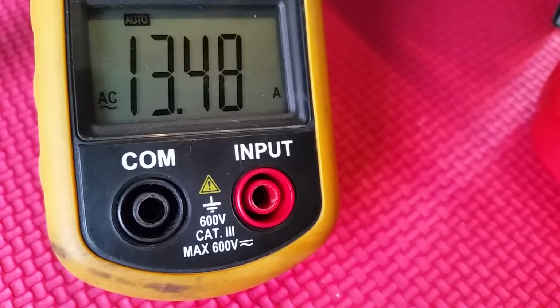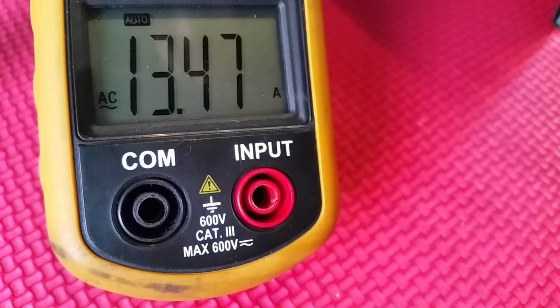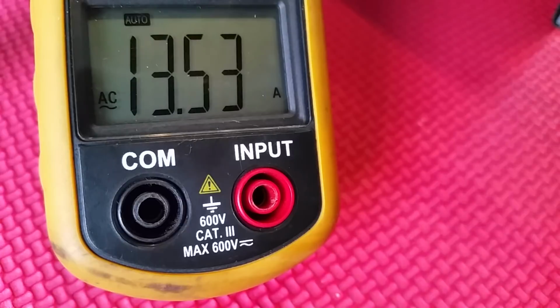Load says it should be set to 12 amps, and I'm getting 13.5 amps. Okay, so far so good. Let me do another double check here... more than 40 amps on the DC load, 68.4 amps.